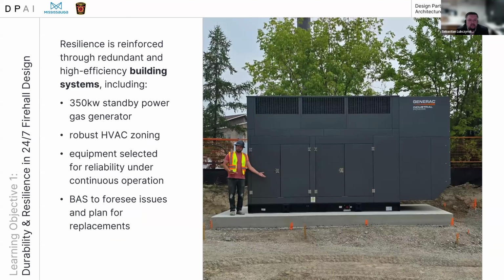Looking beyond layout and finishes, resilience is embedded into the building systems. The HVAC strategy uses clear zoning so different parts of the station can operate independently and respond to varying occupancy and use patterns. The apparatus bay uses a radiant floor heating system, which supports rapid temperature recovery after winter deployments, helping stabilize the space when trucks return cold.